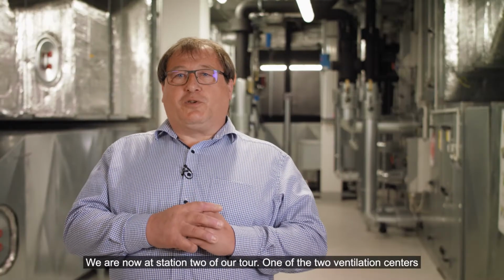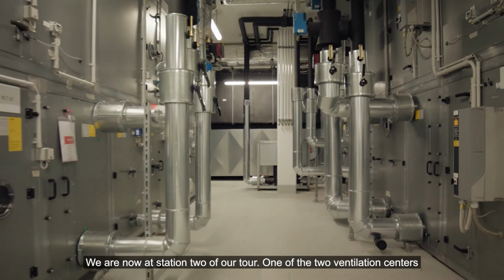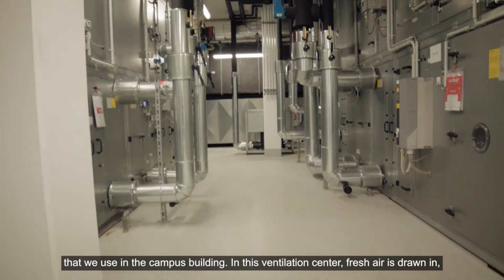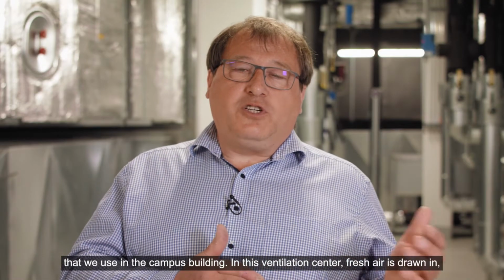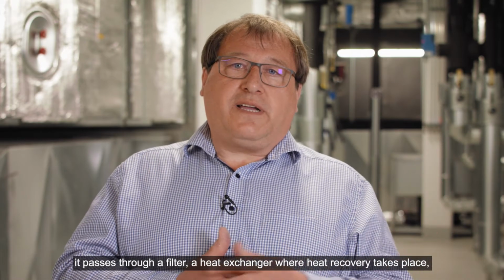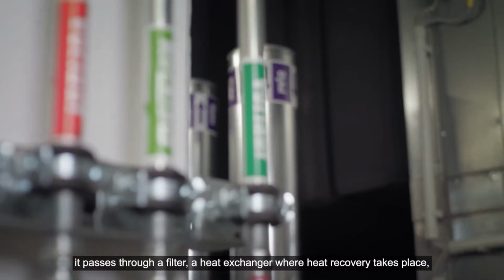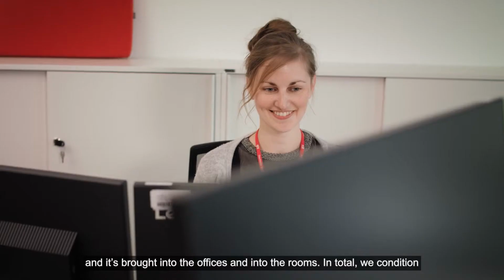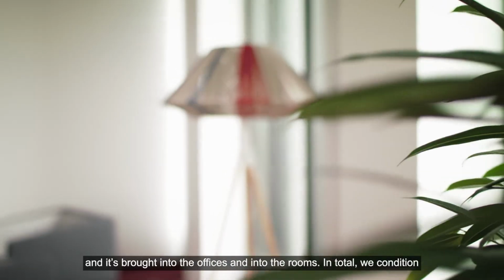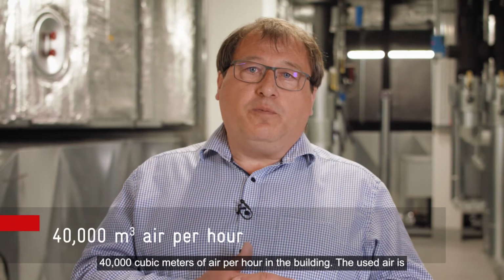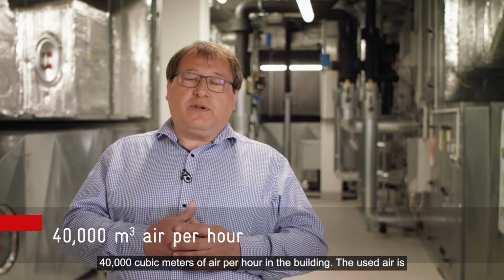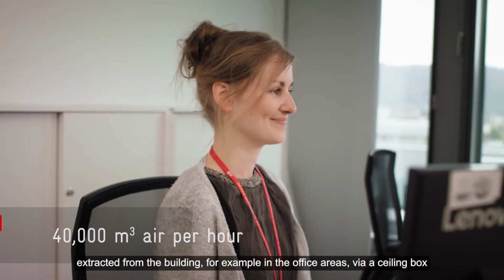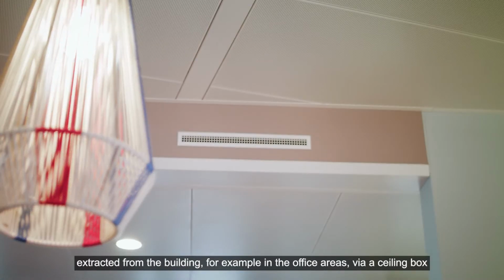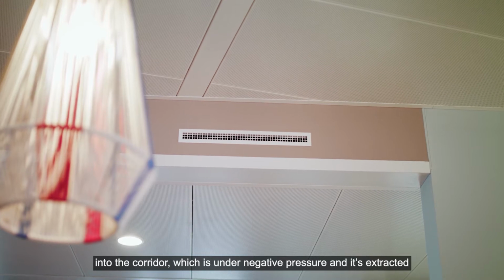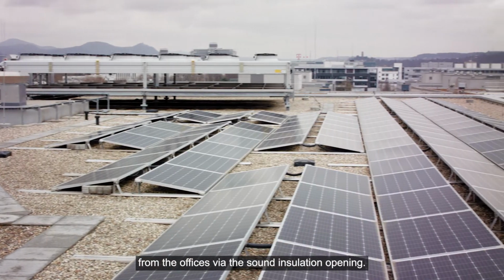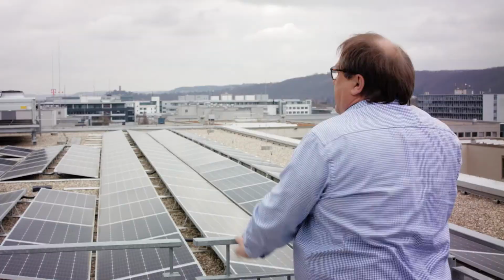We are now at station 2 of our tour, one of the 2 ventilation centers that we use in the campus building. In this ventilation center, fresh air is drawn in. It passes through a filter, a heat exchanger, where heat recovery takes place, and it's brought into the offices and into the rooms. In total, we condition 40,000 cubic meters of air per hour in the building. The used air is extracted from the building, for example in the office areas, via a ceiling box into the corridor, which is under negative pressure, and it's extracted from the offices via the sound insulation opening.